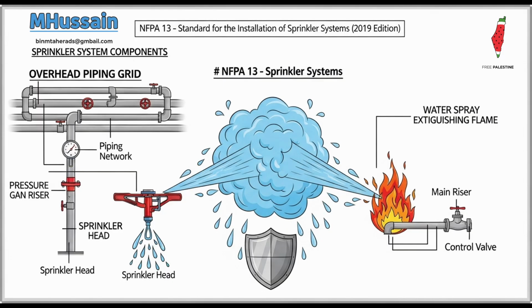We spend so much time focusing on PSI and flow rates, but what about the silent killer, corrosion? Is NFPA 13 finally getting serious about long-term system integrity? It really is, because corrosion, specifically something called microbiologically influenced corrosion, or MIC, is a major cause of failure in older systems. And MIC isn't just standard rust, it's actually caused by living bacteria that colonize the pipe walls. They create these concentrated corrosive environments, leading to pinhole leaks or even system blockage over time. So what does NFPA 13 actually mandate regarding mitigation, especially when you're dealing with potentially high-risk water supplies? Well, the document defines a raw water source as a supply that hasn't been treated and could contain foreign material, which increases the risk of MIC. And if the water supply or maybe the environmental conditions are known to be corrosive, the owner must notify the installer. And then a formal corrosion mitigation plan has to be developed.